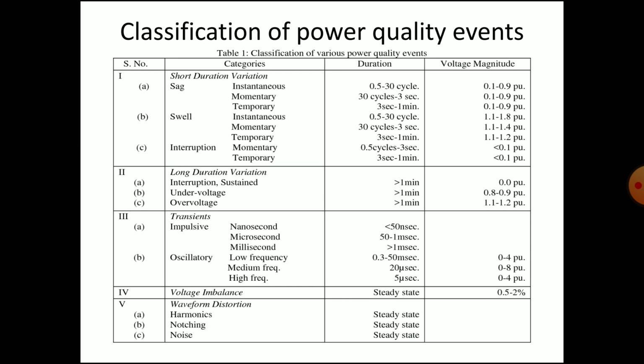Next is voltage imbalance, which is steady state, continuous voltage imbalance. The RYB phases are not receiving a constant voltage input from the utility. There is voltage imbalance. Next is waveform distortion. That includes harmonics, notching, and noise, which are steady state. So this is a general classification of the power quality events which are happening due to the certain causes that we have discussed. And these are the 5 subcategories of power quality events: short duration variation, long duration variation, transients, voltage imbalance, and waveform distortion.